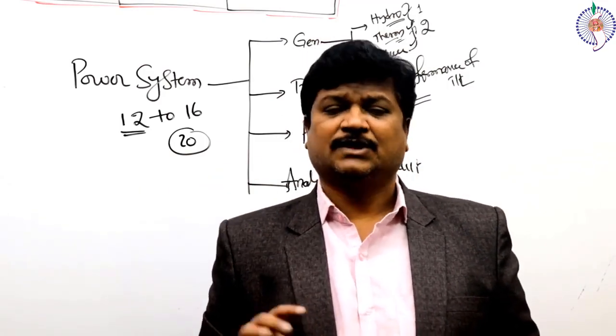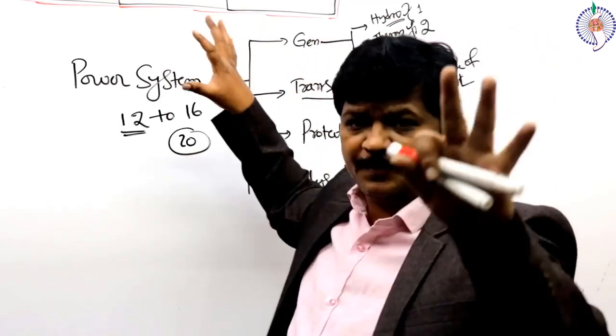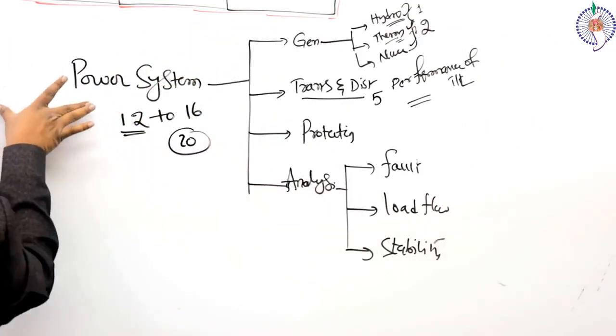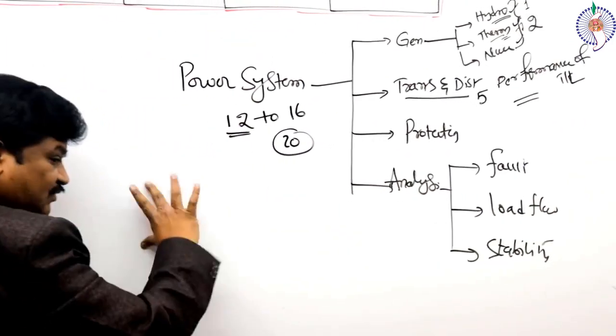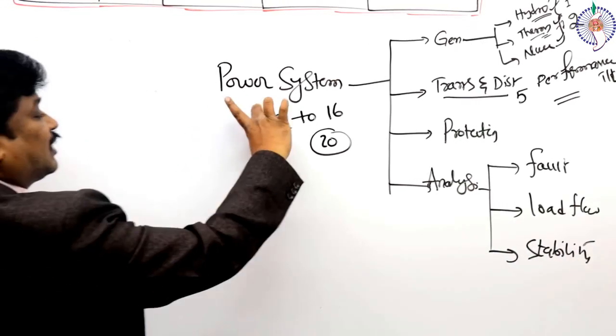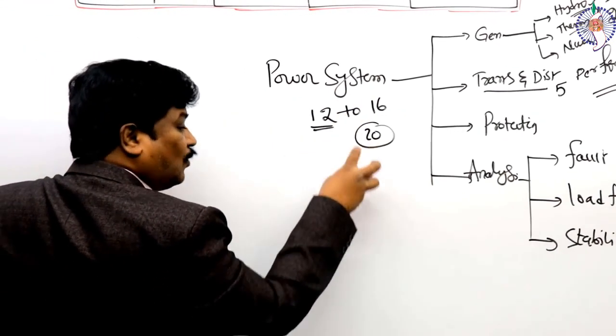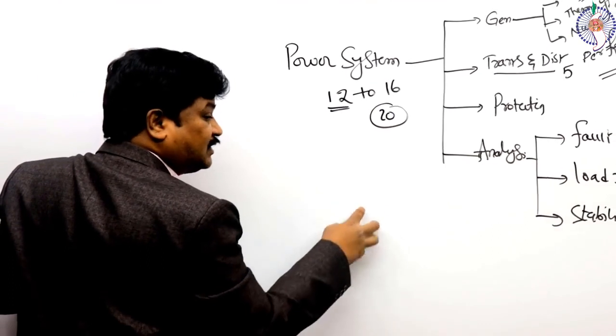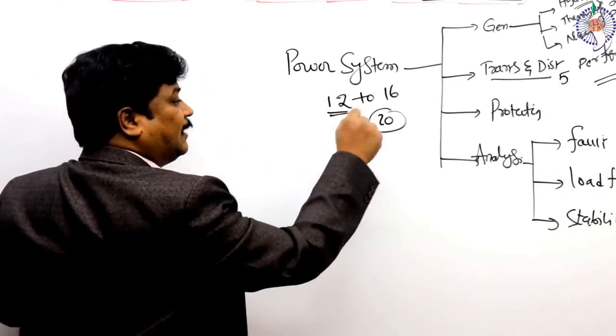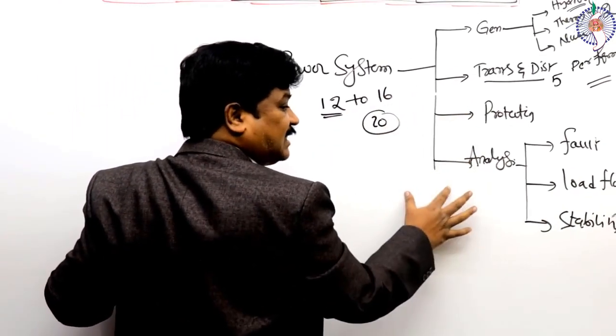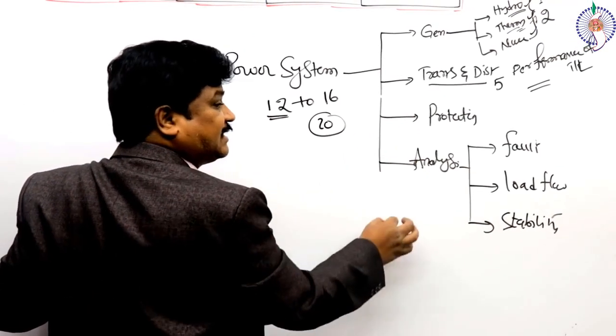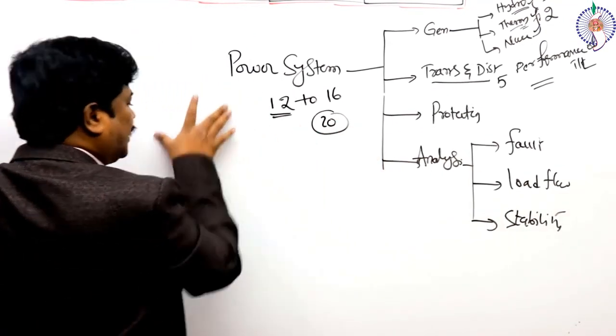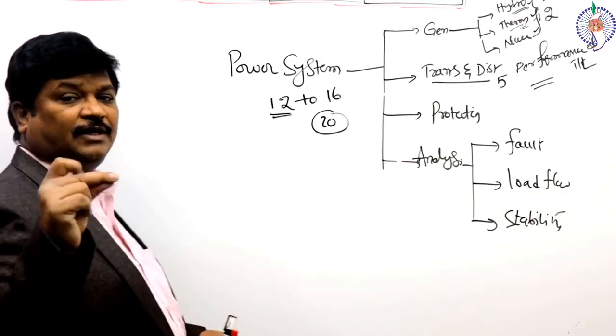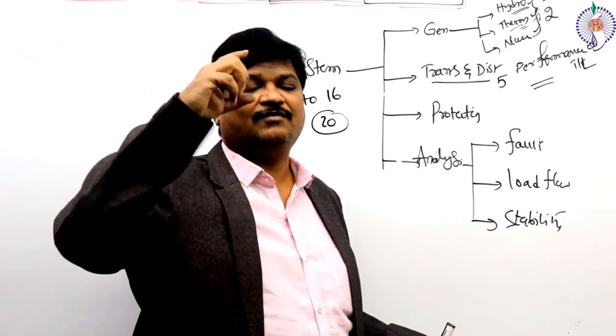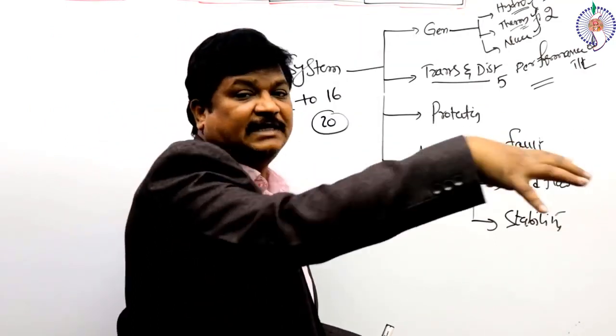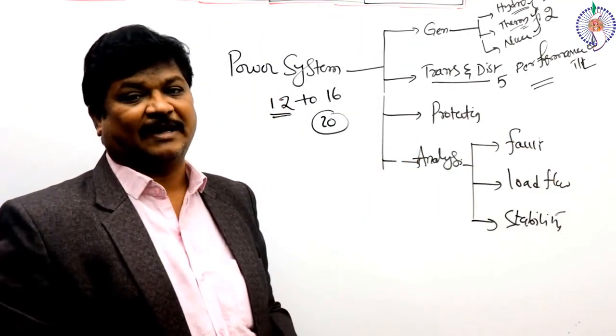For transformer, you can prepare an outline. If you are preparing, you should have a table. Suppose protection of transmission line - what relays are we using? What are the conclusions for protection of alternator - stator side, rotor side - what relays are we using? Positive sequence, negative sequence, what currents, what type of relay - coming to the transformer, Buchholz relay, differential relay, 3-phase transformer connections and applications, overfluxing relay. If you take outlines and tables like this, your mind will give a very good, correct answer in the examination hall. Such clarity is required.